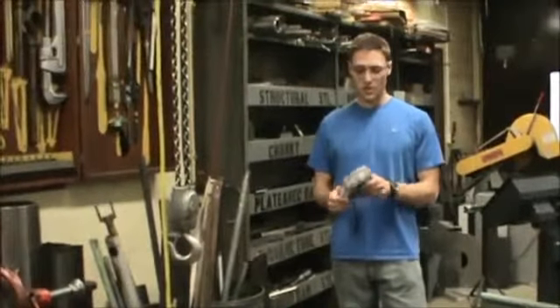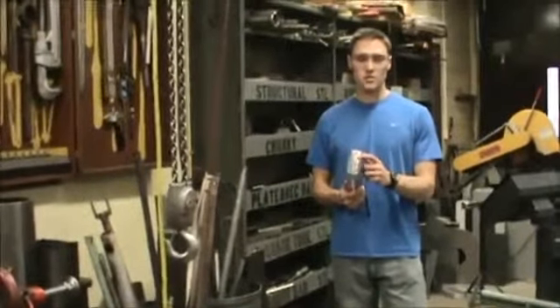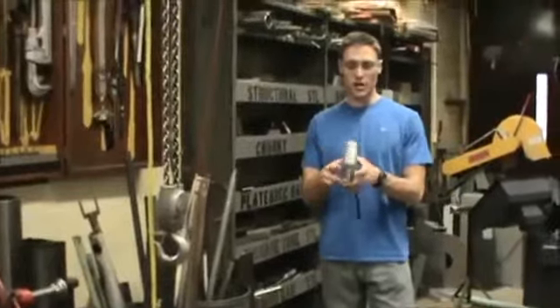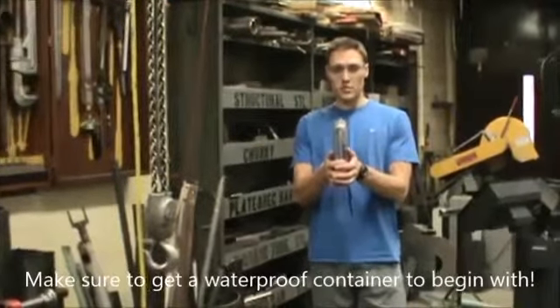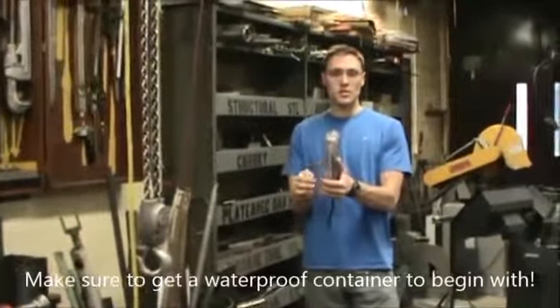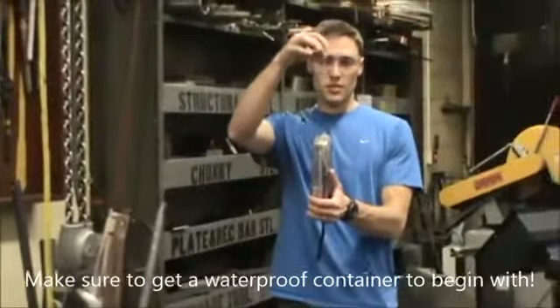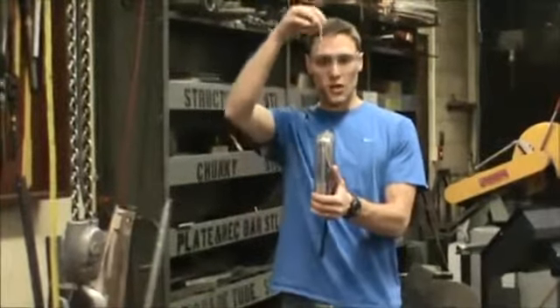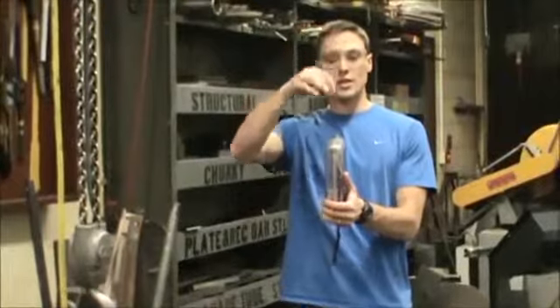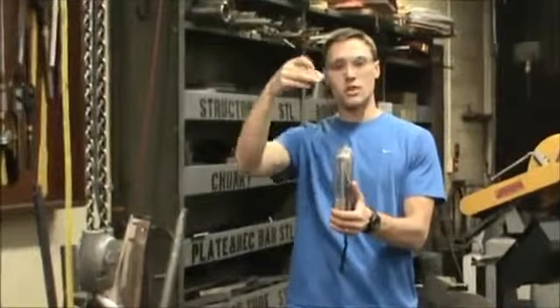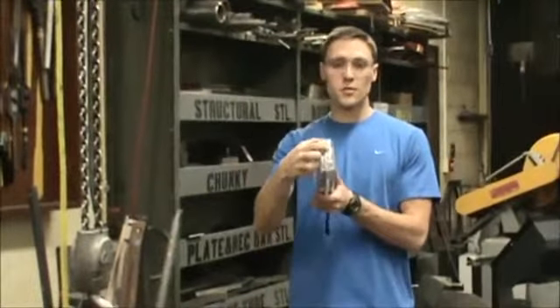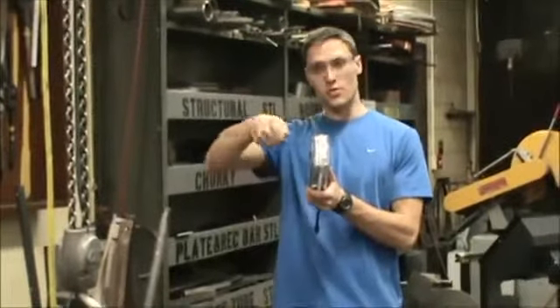In order to drill our hole for our pressure transducer is pretty easy. All we've got to do is take this box, mount it in a vise so it's vertical, and then use a drill or a drill press to come down and put a small hole, then get a slightly larger drill bit, larger hole, larger hole, until we get one that's big enough for the pressure transducer to thread into.